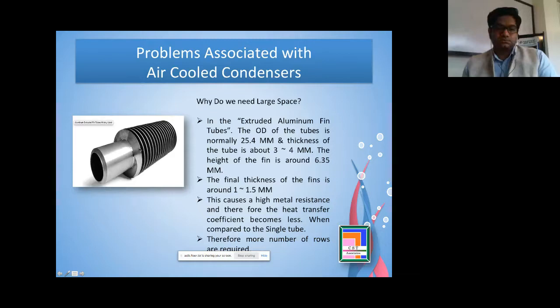The thickness of the tube is about 3 to 4 millimeter, and the fin is 1.1 to 1.5 millimeter. So what happens is, when the steam enters here and the air is blowing from outside, there is a big metal resistance, because the steam has to heat the pipe first, and then it has to transmit that heat to the fins, and the air which is blowing outside has to dissipate that heat. This is the reason these extruded fin tubes are installed in 3 row, 4 row, 5 row, 6 row arrangements, something like that.